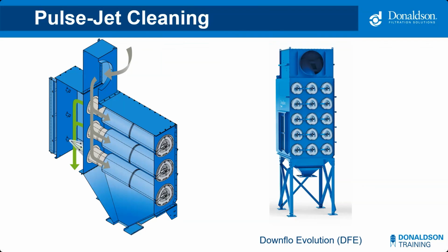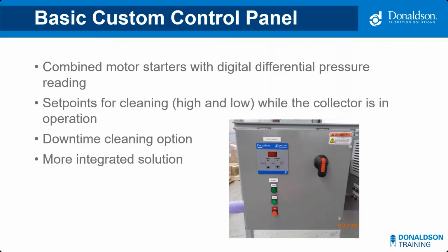When enough dust is built up on the filters, this is monitored via a pressure gauge, either digital or analog, a quick cleaning pulse occurs, and the air pulses the dirt off the filters into a collection bin at the bottom. A pulse jet cleaning collector will typically use a basic custom control panel. Essentially, it combines the motor starters with a digital differential pressure reading. This allows the operator to determine set points for cleaning, both high and low. High would be when the cleaning is initiated, and low when the cleaning is stopped.